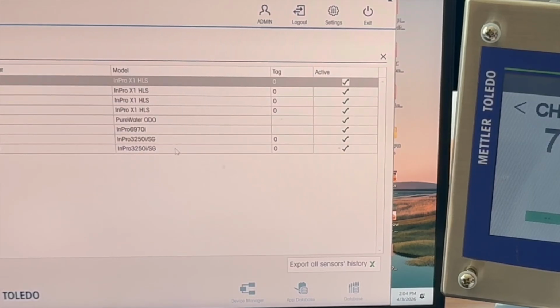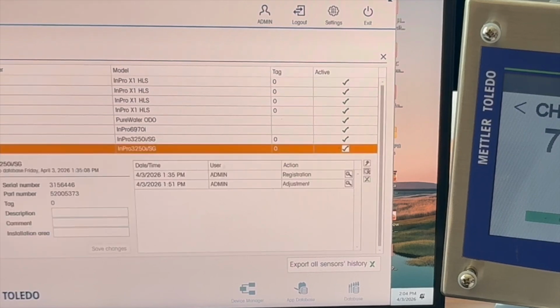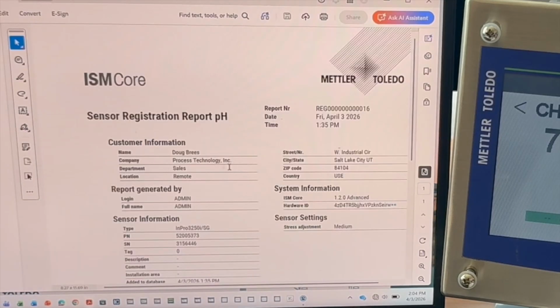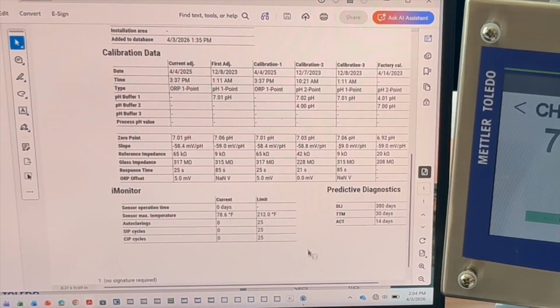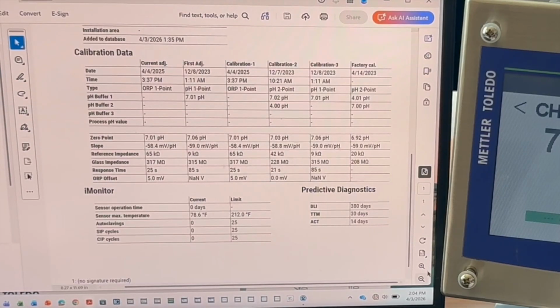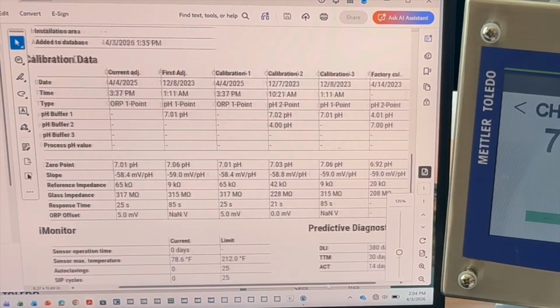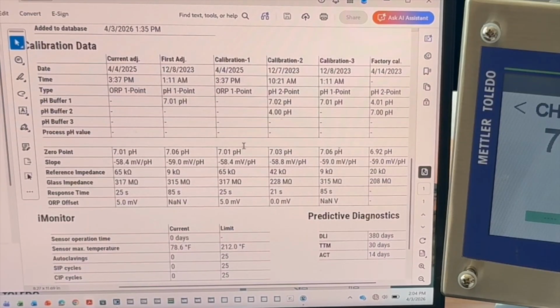If we look at the probe we just had, which was this one at the bottom, I can click on a function here to get the report of this sensor. I can zoom in a bit here. And what we can see is actual data from this sensor. When it's taken out of the box and calibrated for the first time, this is really important for end users. When they do that first calibration, it's burned into the memory permanently. It's called the first adjustment. The reason is that that's the baseline data that all data of the sensor aging is compared to.